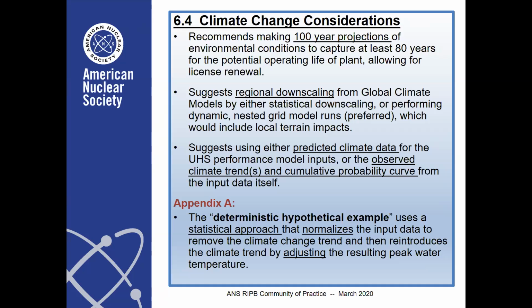The predicted climate data for the UHS performance model inputs, we would suggest that the cumulative probability curve is a very useful way of handling that, rather than just taking the results out of a report, say, and saying, okay, it says temperature is going to be 5 degrees warmer, let's go bump our numbers up 5 degrees. It would be better to do your statistics, or I should say probabilities, on that side before you do that modeling.